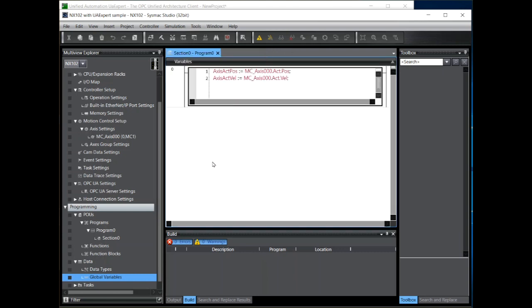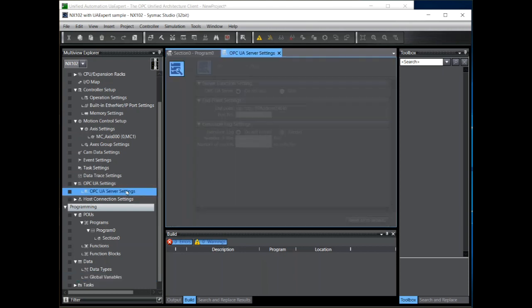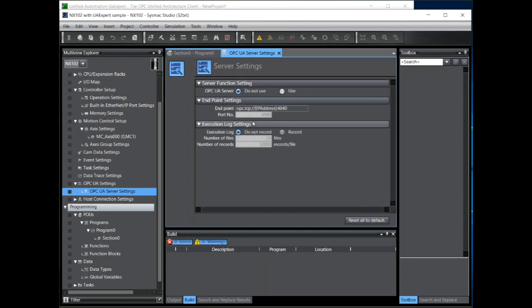Now we can set up the OPC UA server itself. To do that in the configuration and settings window we go to OPC UA server settings here. Double click. These are the defaults. Default is not to use the server, so we click the use radio button. Notice the port number. The default port number of 4840 is used by OPC UA TCP and UDP traffic.